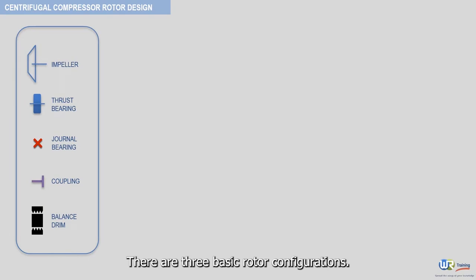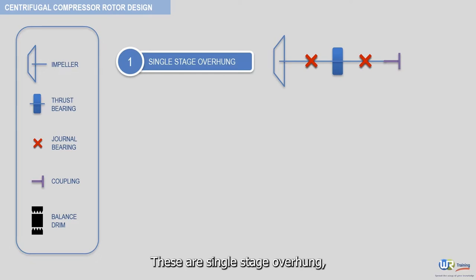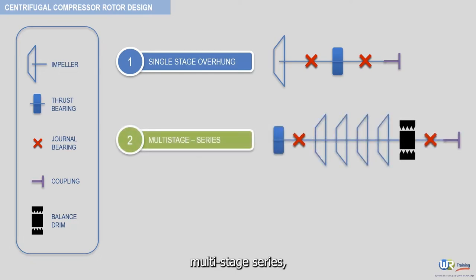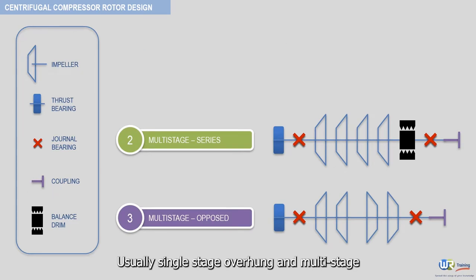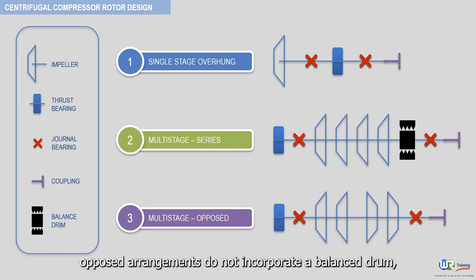There are three basic rotor configurations: single stage overhung, multi-stage series, and multi-stage opposed arrangements as depicted here. Usually, single stage overhung and multi-stage opposed arrangements do not incorporate a balance drum.